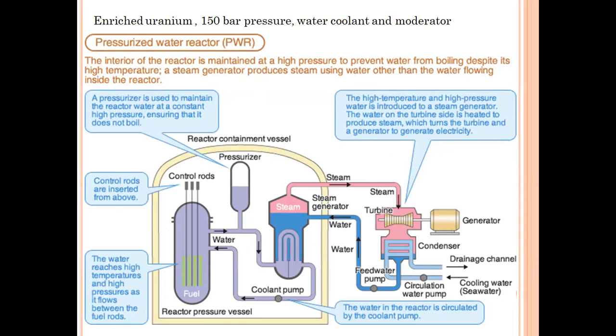We can see here the pressurized water reactor. A pressurizer is used to maintain the reactor water at a constant high pressure, ensuring that it does not boil. Now see here, control rods are inserted from above. The reactor water reaches high temperature and high pressure as it flows between the fuel rods. The high temperature and high pressure water is introduced to a steam generator. The water on the turbine side is heated to produce steam, which turns the turbine and generator to generate electricity.